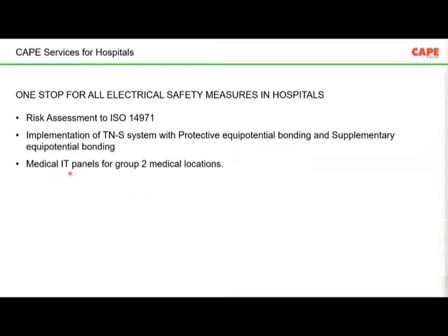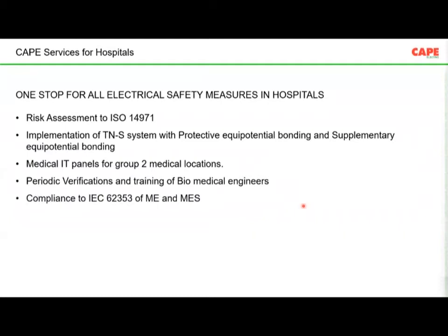We carried this out. Medical IT panels for group 2 medical locations, because when we offer all the services, a medical IT panel is also one of the requirements. So this also we are offering. Then periodic verification and training of biomedical engineers. Sometimes you may have to check your UPS and your generator once in 3 months or once in 6 months. So calling a third party and doing this test will be quite difficult. Also, imagine you are having new equipment every time. Depending on a third party will be very difficult. So we train your biomedical engineers to handle the day-to-day needs of the technical requirements.